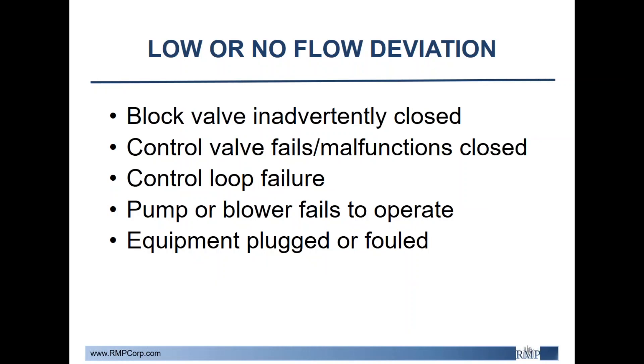The first deviation is low or no flow. Common causes include block or control valves malfunctioning or being inadvertently closed — either by an operator or due to mechanical failure, possibly from loss of power. It is important to note whether valves are normally closed or normally open, as well as their fail-safe positions, as a good P&ID would indicate these. Other causes in a low flow deviation include control loop failures, pumps or blowers failing to operate, or equipment getting plugged or fouled, such as filters, strainers, or heat exchangers.